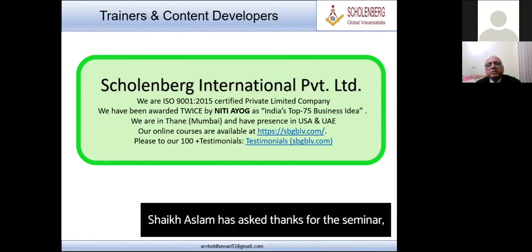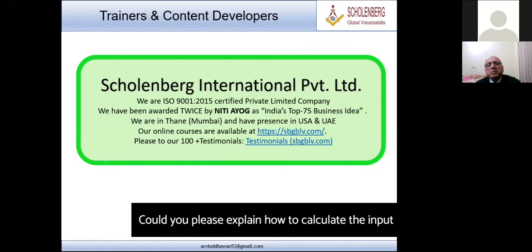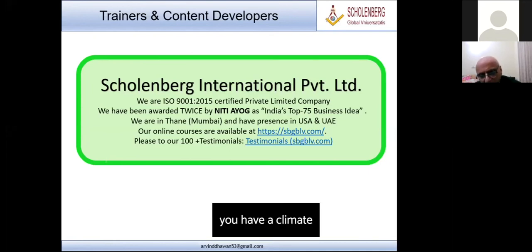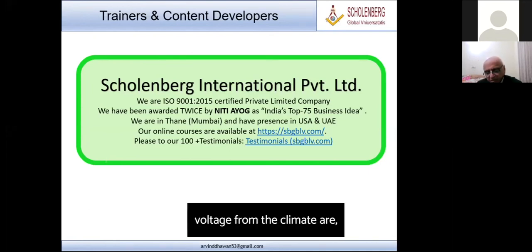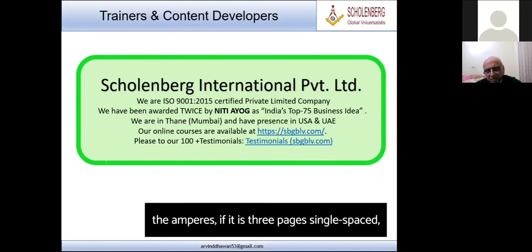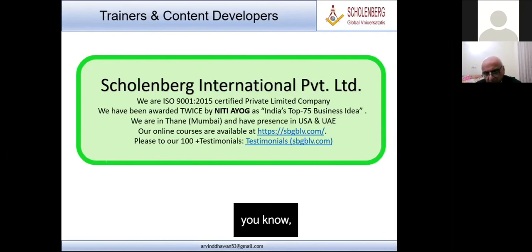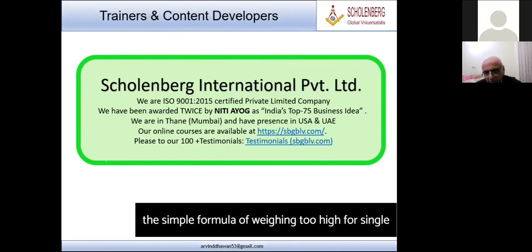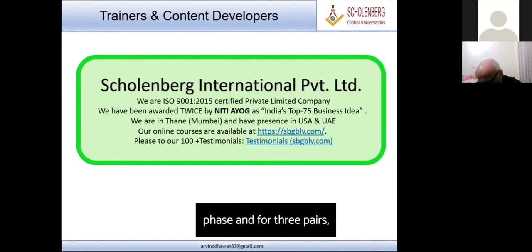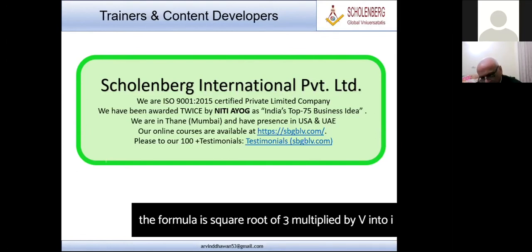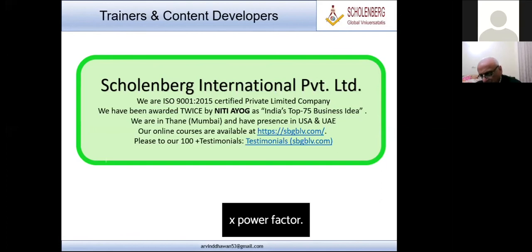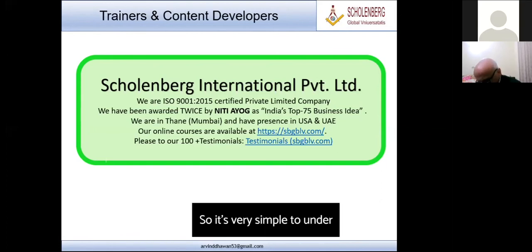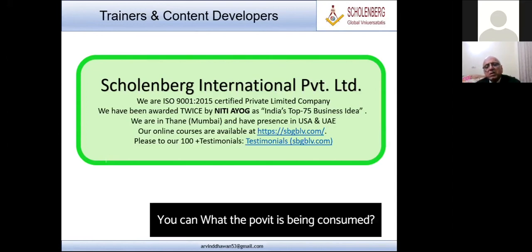Mr. Sheikh Aslam has asked, thanks for the seminar. Could you please explain how to calculate the input electrical power for chiller and corresponding pumps? Yeah, you have a clamp meter, you know voltage from the clamp meter, you know the amperes. If it is single phase, there's a simple formula of V into I, and for three phase, the formula is square root of 3 multiplied by V into I multiplied by power factor. So it's very simple to calculate how much power is being consumed.